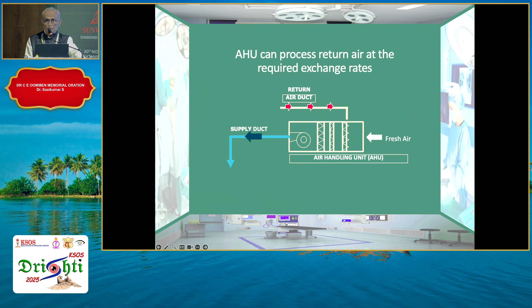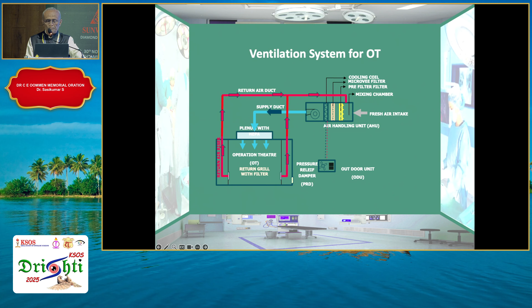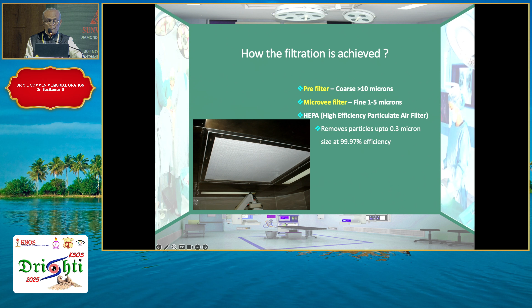If a laminar flow unit is incorporated, which essentially is a box with a terminal HEPA filter placed above the surgical field, further filtering of particles up to 0.3 microns is possible, and it supplies a unidirectional stream of air at the surgical site. The pre-filter can filter up to 10 microns, the micron filter up to 1 micron, and then there is the HEPA filter, or high efficiency particulate air filter. This usually has a perforated metal sheet for protection.